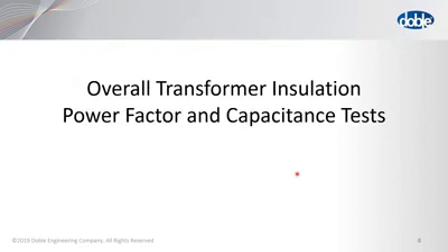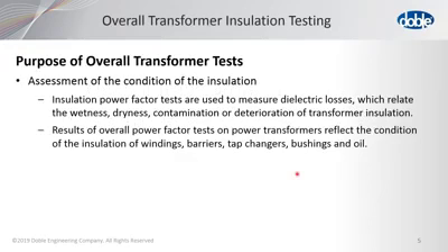So, overall transformer insulation, power factor, and capacitance tests. Now, why do we do these tests? We're testing the overall insulation of the transformer, and what we're trying to do is assess the condition of that insulation. We found that during these power factor tests the dielectric losses and the percentage of power factor are related to the wetness or the dryness of the insulation, and whether there's any contamination or deterioration of that insulation. So over time you can identify if your insulation is becoming contaminated or deteriorated. It's a very important test to perform. And results of the overall power factor test can reflect the condition of the windings, the barriers, tap changers, bushings, and oil. I'll go into some detail further on and explain how these are identified.